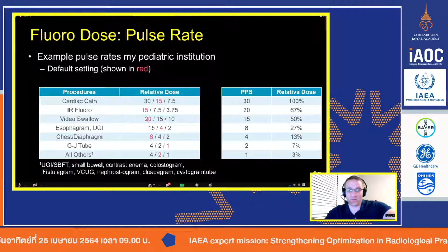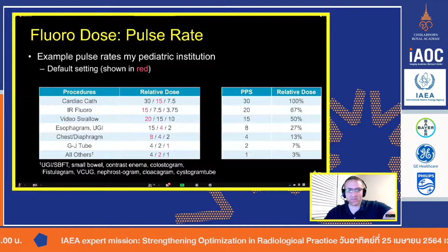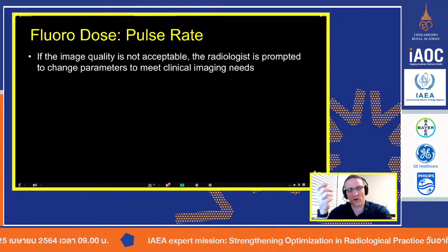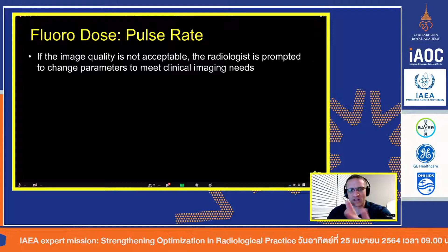We use 20 as our default for our video swallows. But if they really wanted to, for whatever reason, they could go to 15 and 10, and you see all the other examples. The reality is, if you set the pulse rate low initially, and the radiologist or the operator walks in and starts working with the machine and thinks, I just can't quite see or do what I want, they obviously have the option to go up. In our case, they have 2 more elevated dose options. But the opposite is rarely true.